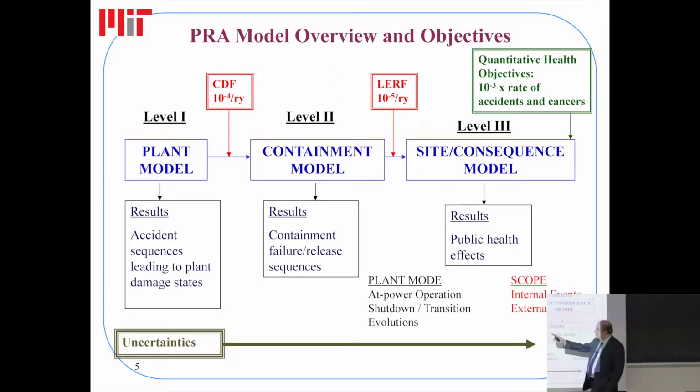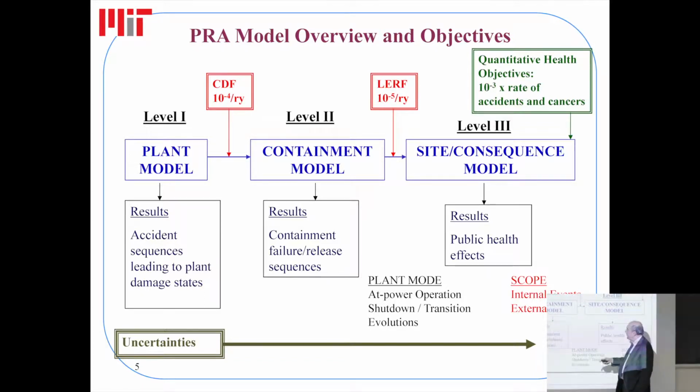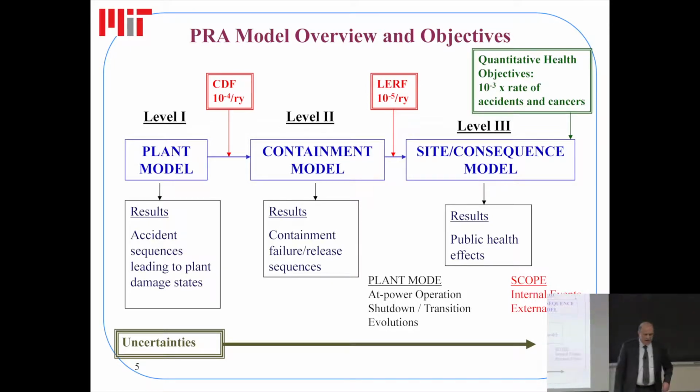Once you have these accident sequences, and you have already damaged the fuel, you enter the level 2, which is the containment model. And the science is different here. In the plant model, you have a lot of Boolean algebra. This pump works, it doesn't work, the valve works, it doesn't work, and you create the sequences.